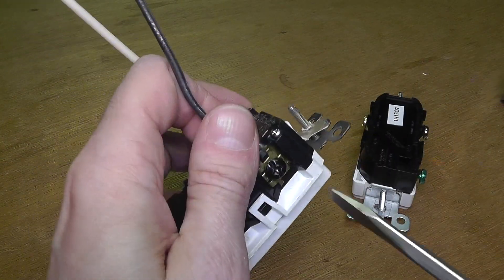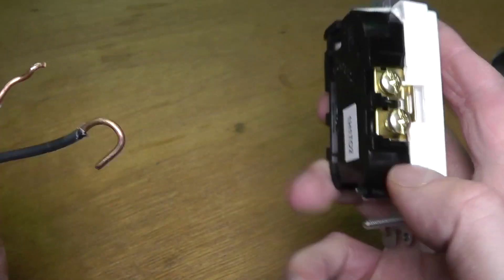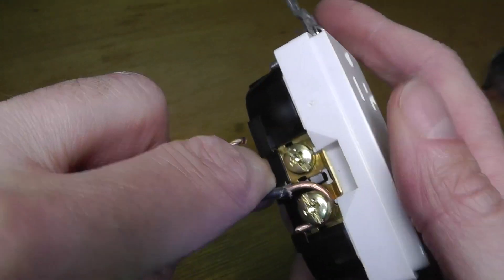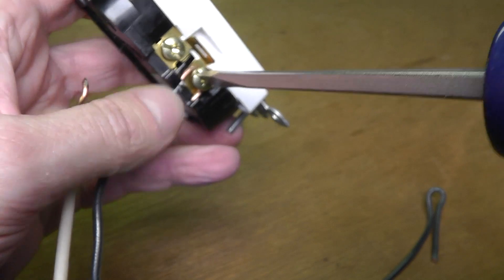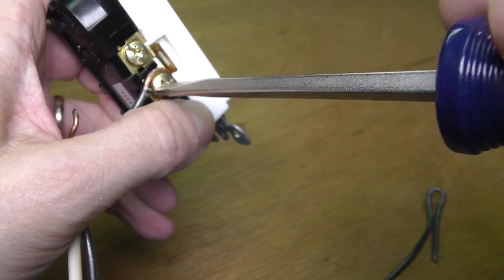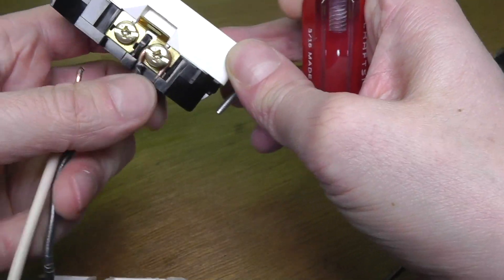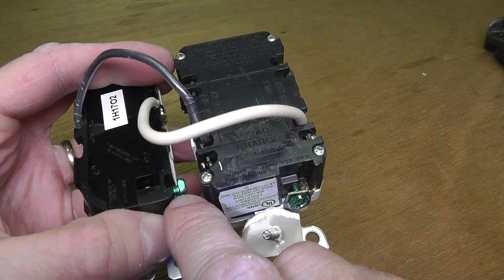Now I do the same for the black hot wire on the opposite side at the brass screw. For the second regular outlet, I created a hook at the end of the wire and wrap it around the hot screw in a clockwise direction, so that tightening the screw helps pull the copper wire firmly around it. I repeat the same process for the neutral wire as well.